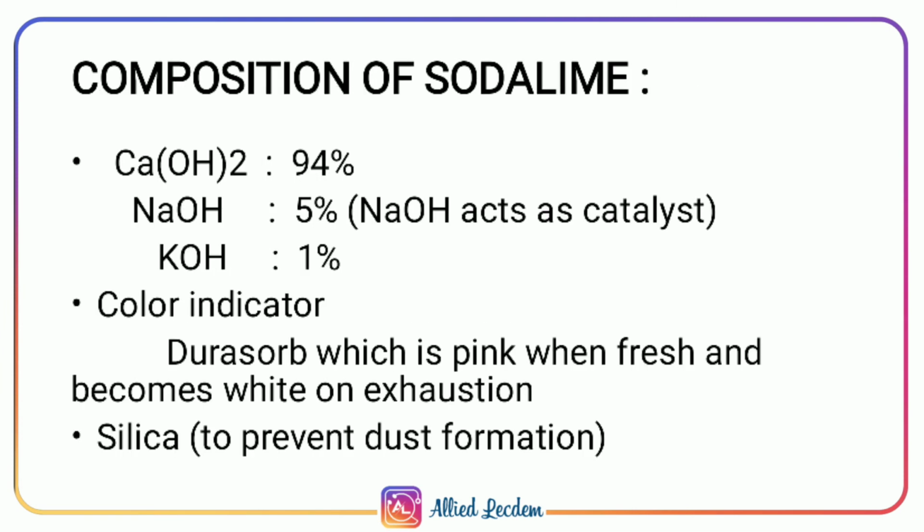The traditional composition of soda lime is calcium hydroxide 94%, sodium hydroxide 5%, potassium hydroxide 1%. The color of the soda lime would be pink when fresh and white on exhaustion. To prevent dust formation among the granules, we have silica in it.